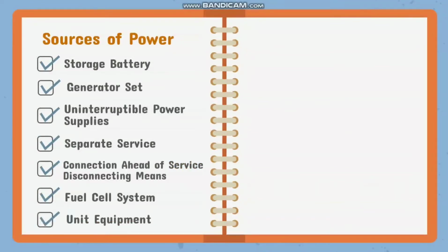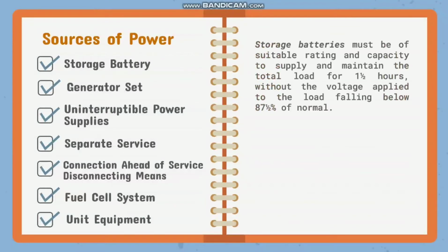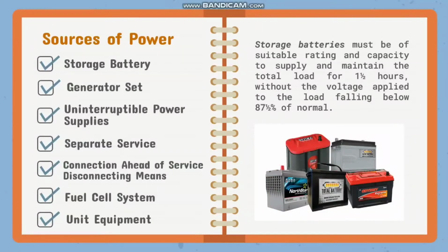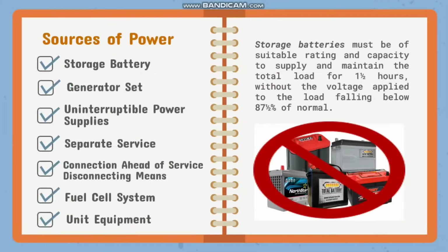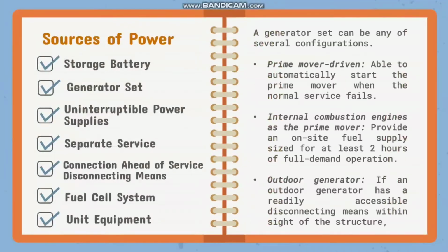For storage batteries, they must be of suitable rating and capacity to supply and maintain the total load for 1.5 hours without the voltage applied to the load falling below 87.5% of normal. Also, automotive type batteries shall not be used.